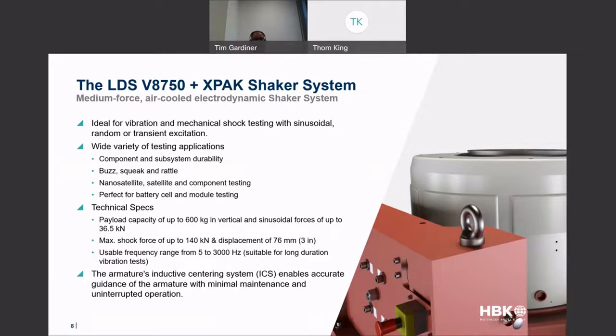We have a large usable frequency range going from 5 to 3000 hertz, making it very suitable for long duration vibration tests. And certainly with the new inductive centering system that enables accurate guidance of the armature with minimal maintenance and uninterrupted operation. The V8750 and XPAK shaker system is available in different configurations to meet all of the different types of requirements out there. It can be used with a head expander for larger payloads in vertical orientation and can be used in combination with a hydrostatic bearing supported slip table for the testing of components on the horizontal plane. But first of all, before we go any further, let's take a look at the shock performance in a little bit more detail.